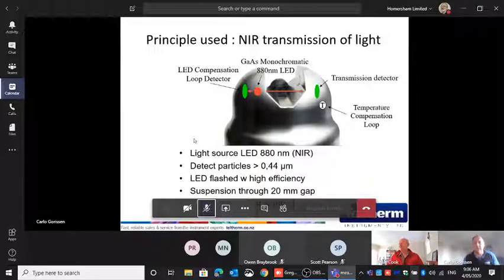That's how you do a calibration, single point with the lab sample. The good thing with the unit is basically that we measure the strength of the LED as well, and we measure the temperature. So we compensate for both. Big gap in the middle, that is basically so we don't have big chunks of whatever get stuck between, because of course, if that happens, you have an issue.